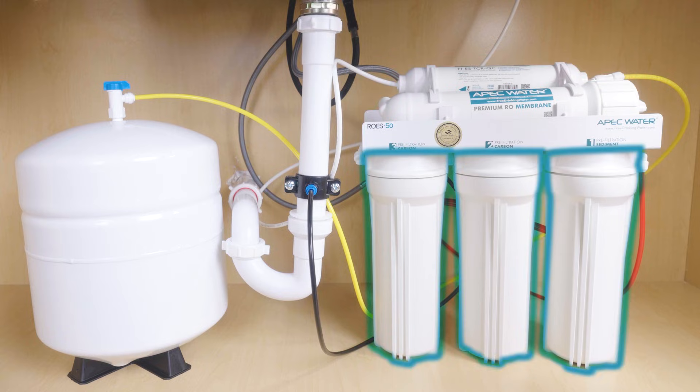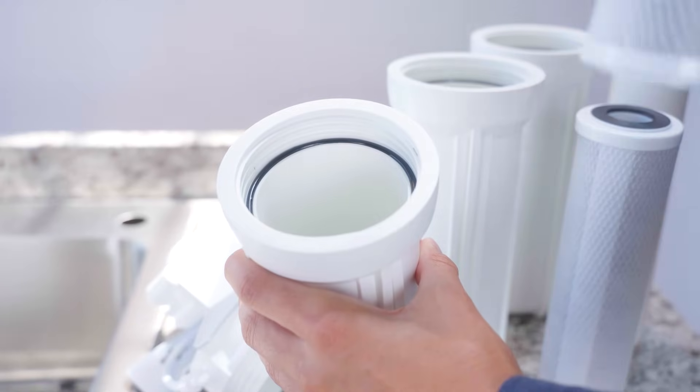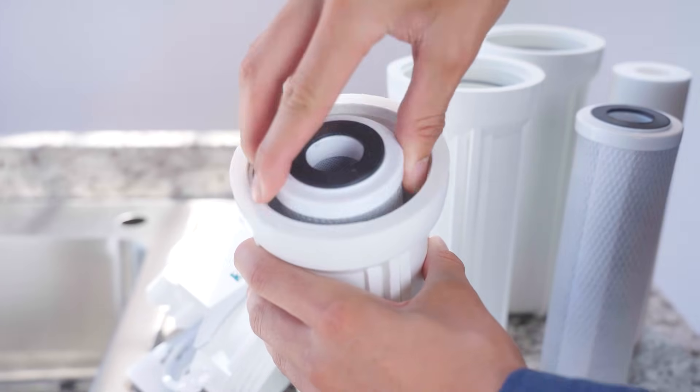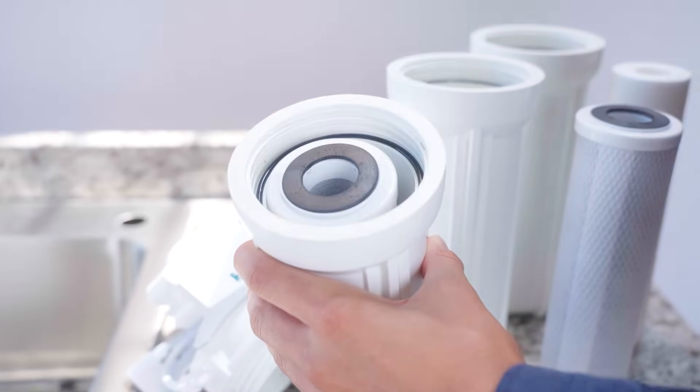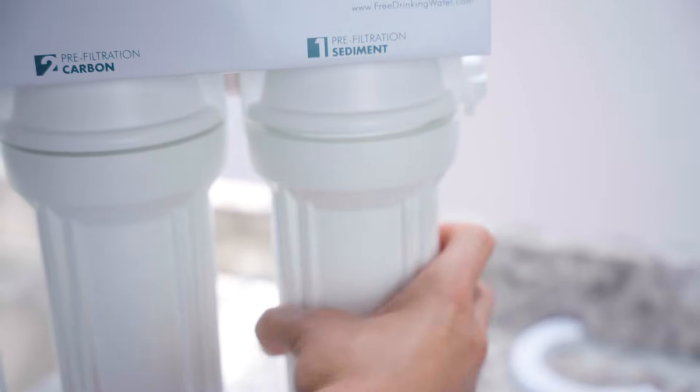Time to load in the filters. Unscrew each housing and drop in the right cartridge. Make sure the O-rings are clean and properly seated. Tighten by hand, firm but not too tight. Use the wrench for just a quarter turn at the end. Don't overdo it. Cracks aren't worth it.